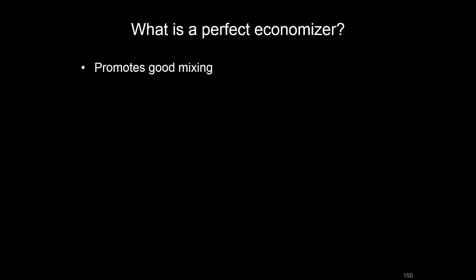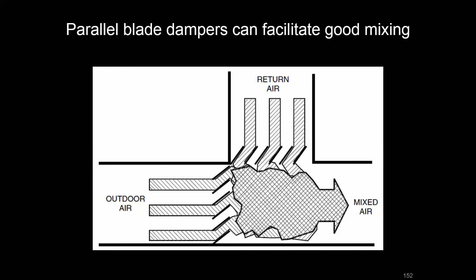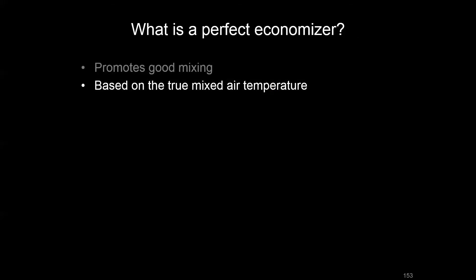First, a perfect economizer would promote good mixing, and there are right ways to do that. With the right damper selection — the size, the relative location to one another, and having a parallel blade type that can redirect air streams to crash into one another — you can have good mixing in your mixed air plenum.